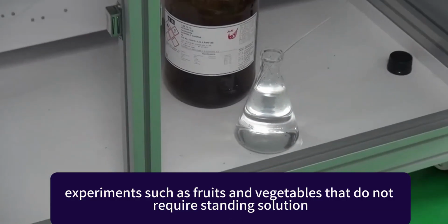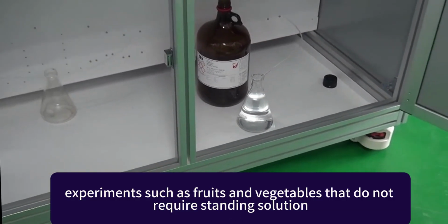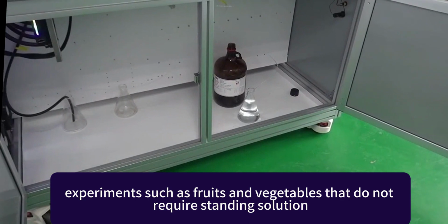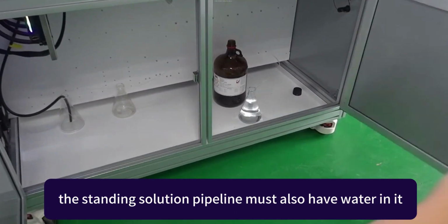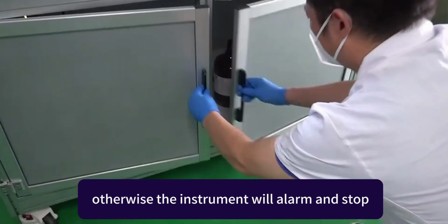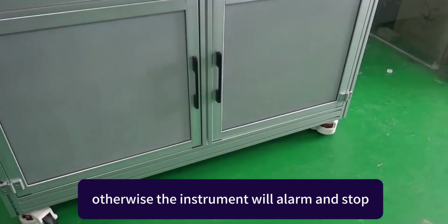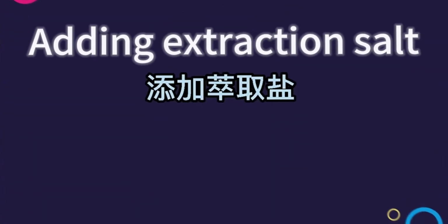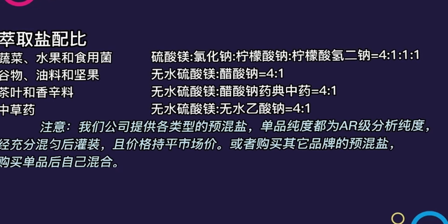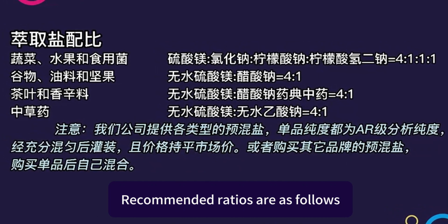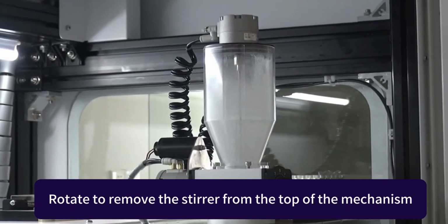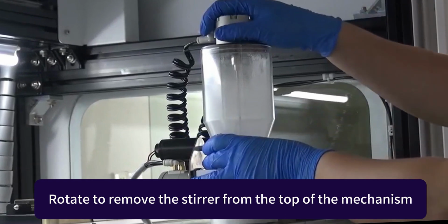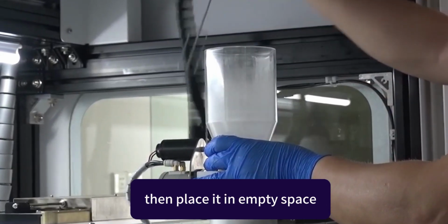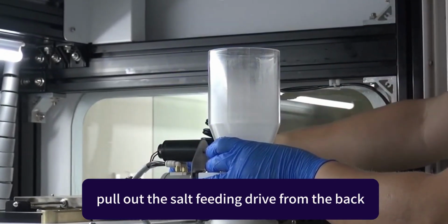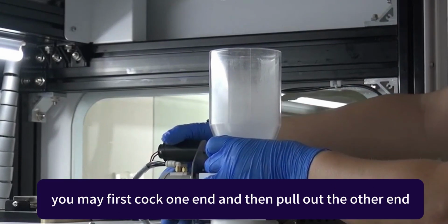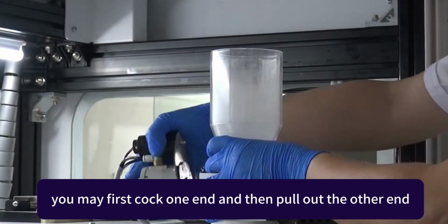Note: experiments such as fruits and vegetables that do not require standing solution, the standing solution pipeline must also have water in it, otherwise the instrument will alarm and stop. Adding extraction salt. Recommended ratios are as follows. Rotate to remove the stirrer from the top of the mechanism, then place it in empty space. Pull out the salt feeding drive from the back. You may first cock one end and then pull out the other end.